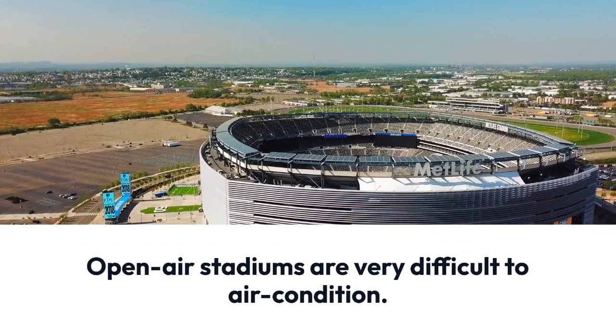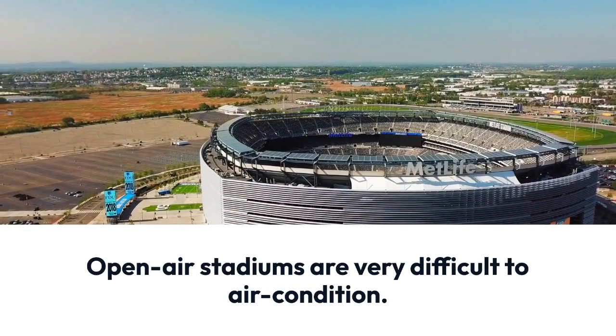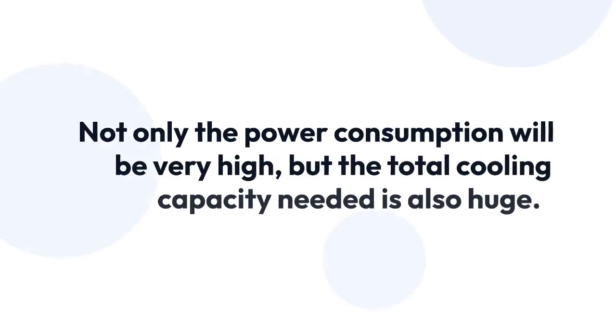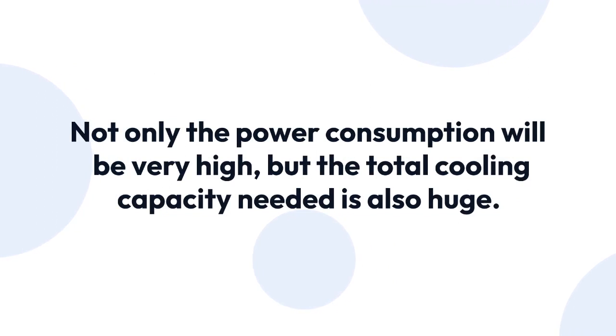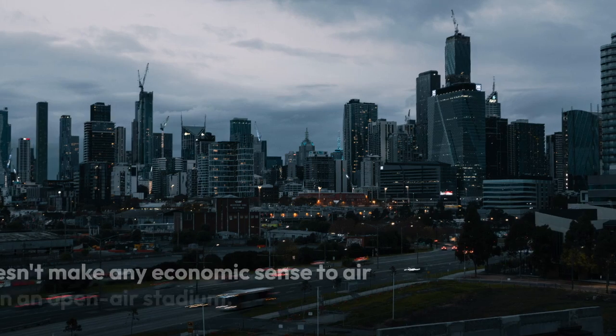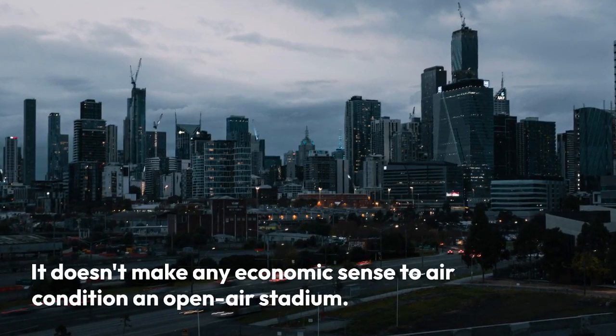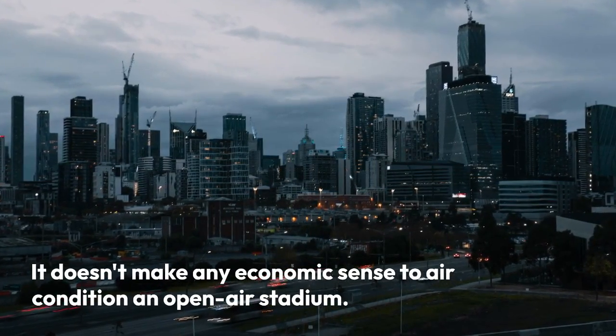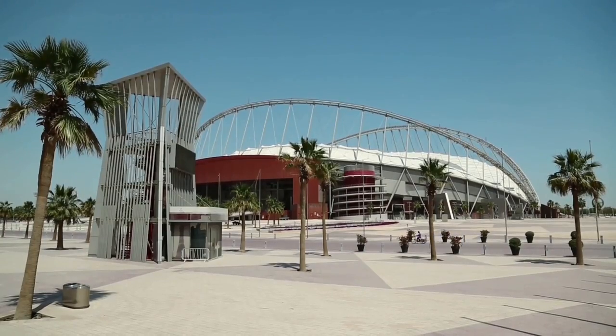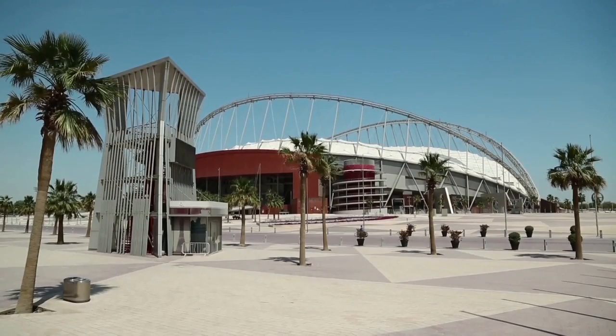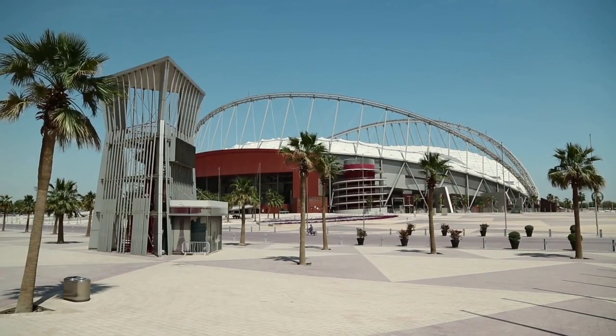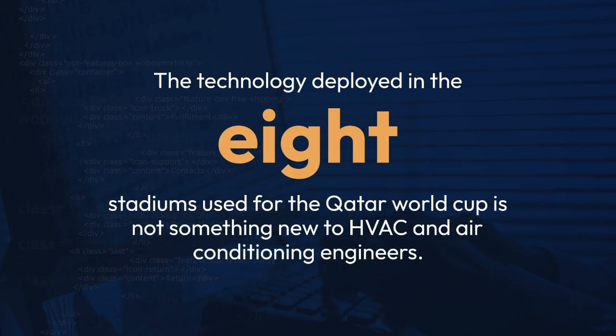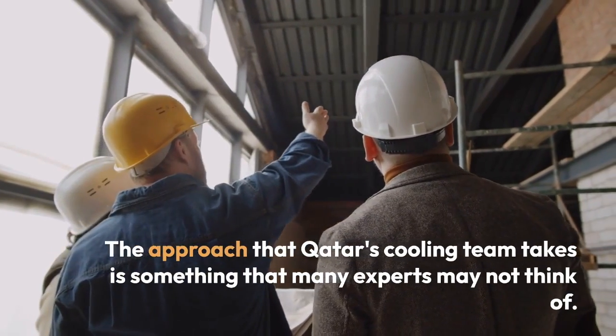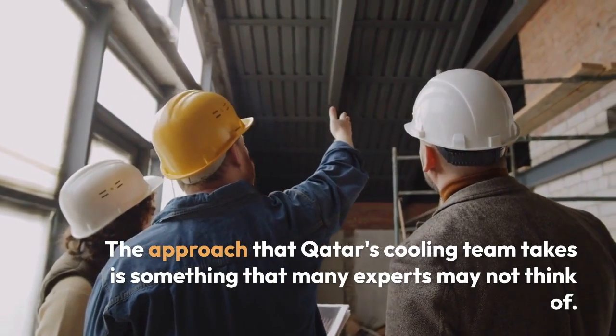Hence, open-air stadiums where the outside air is constantly coming in are very difficult to air condition. Not only will the power consumption be very high, but the total cooling capacity needed is also huge. It doesn't make any economic sense to air condition an open-air stadium. Nonetheless, the 8 open-air stadiums of Qatar are air-conditioned, and the way they did it is brilliant and eye-opening to many HVAC experts. The technology deployed in the 8 stadiums used for the Qatar World Cup is not something new to HVAC and air conditioning engineers.